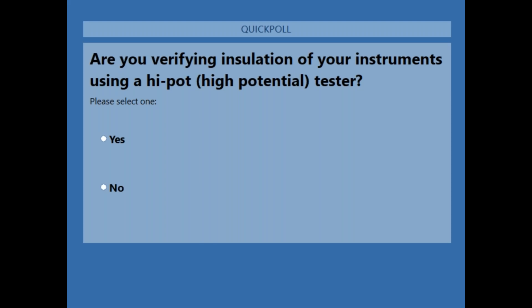I know being at some of the hospitals, they have the instruments, but they only use one voltage setting. So it's important that, for example, insulating shaft or cord may require 4,200 volts or 4.2 kV, while bipolar forceps may use 2,800 volts. Now, some people have those insulation testers, but they only set it up, say, at 1,500 volts, which is not sufficient for some of the instruments.